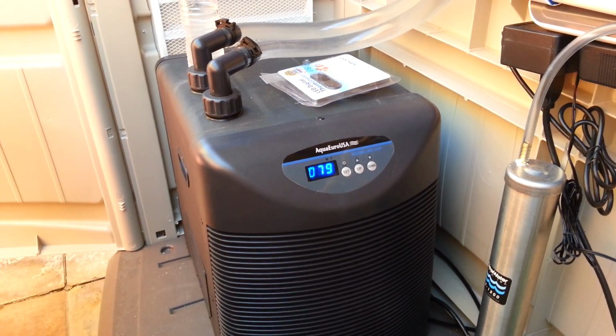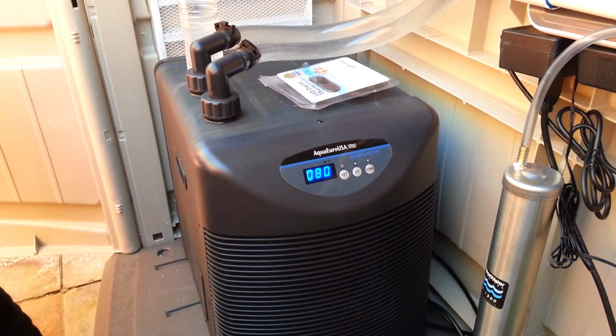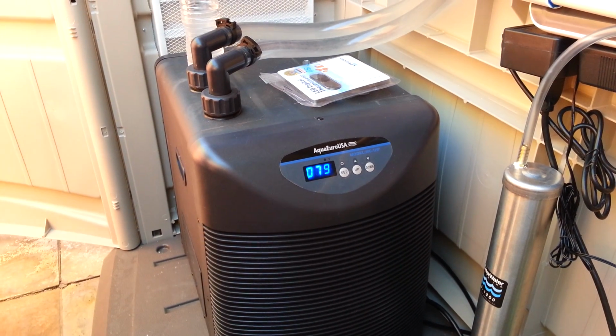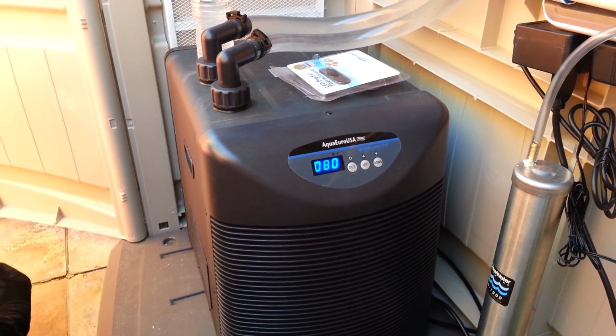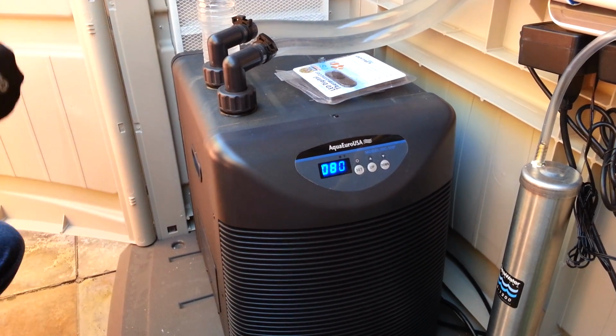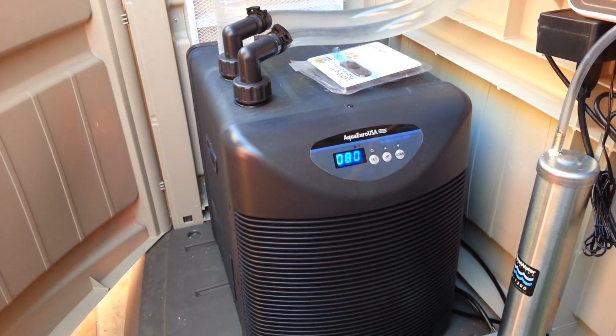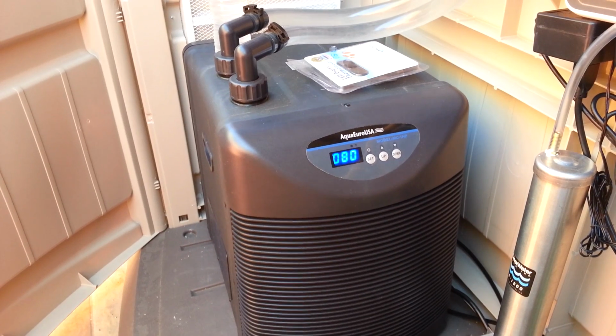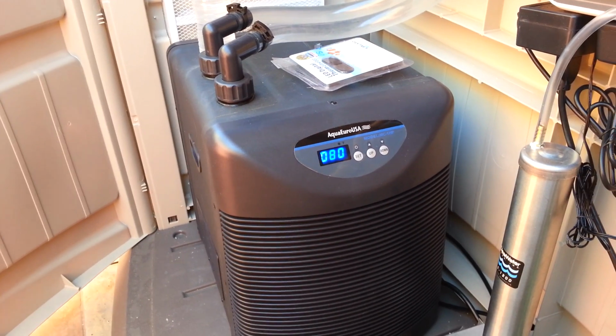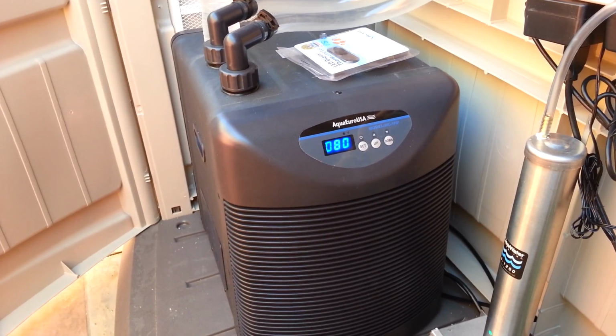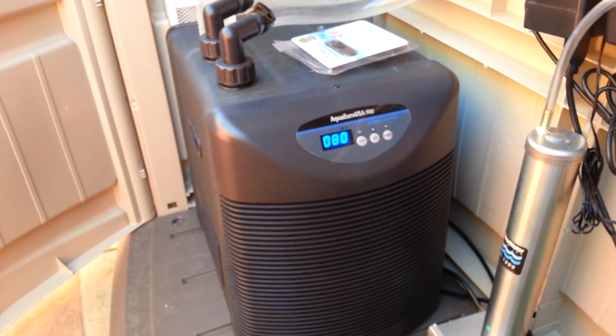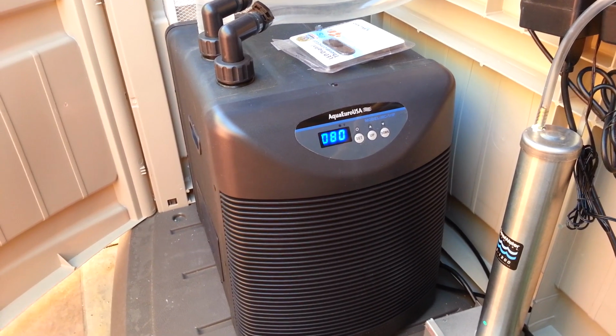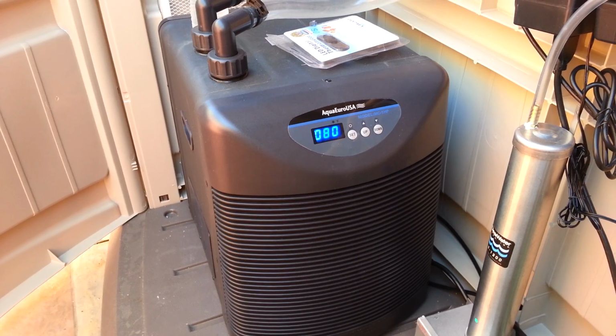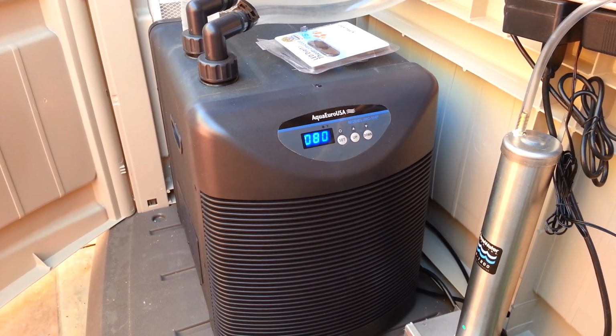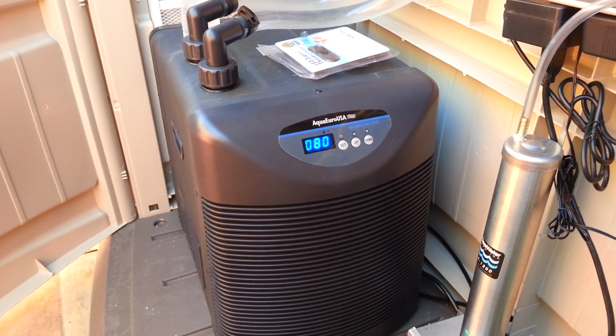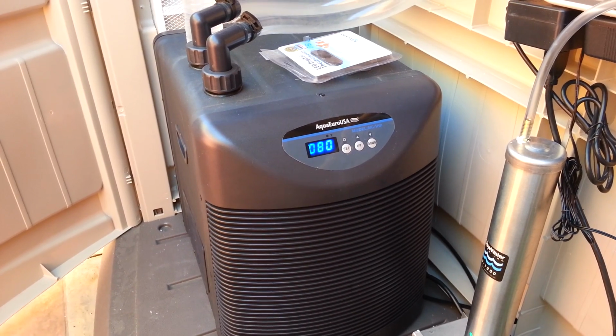It goes up to 80, starts fluctuating, and that was after probably less than a minute, it started to go higher. If I left the video running, it's going to go up to 81, 82. It keeps rising, and then the problem is the chiller doesn't shut off. It just keeps running and running. My customer here said the other day he didn't realize that there was an issue with it, and it was running for a couple of hours straight because it kept getting higher and higher on the readout.